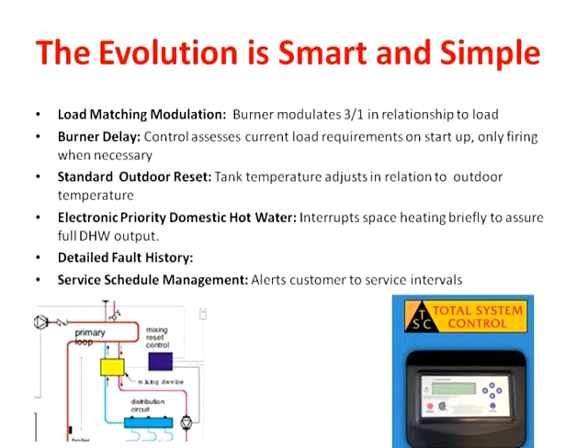It does have an electronic priority domestic hot water, so it actually senses through PID logic when the temperature is falling in the tank at a curve that's consistent with the domestic hot water load, and it will deactivate the pump going to the space heating while that curve exists, and it will automatically go back when the domestic hot water has been satisfied. And it does this actually not just in an on-off type condition. It's going to look at the profile of the curve in order to give the maximum performance.